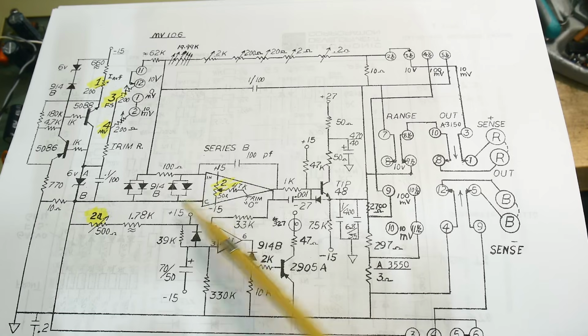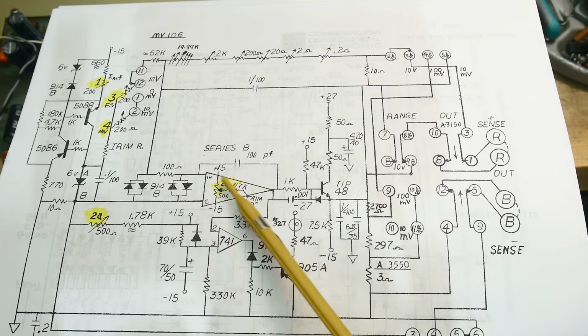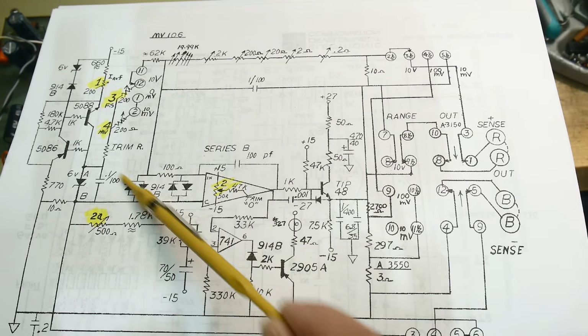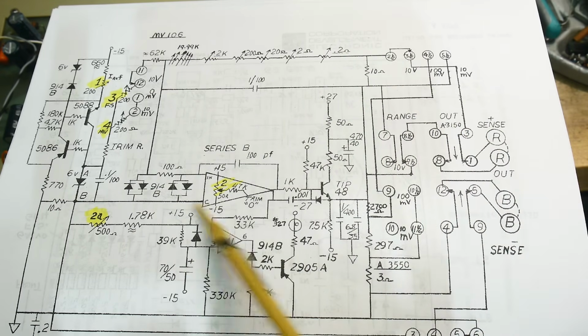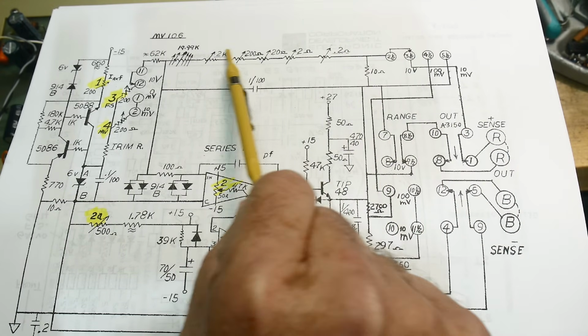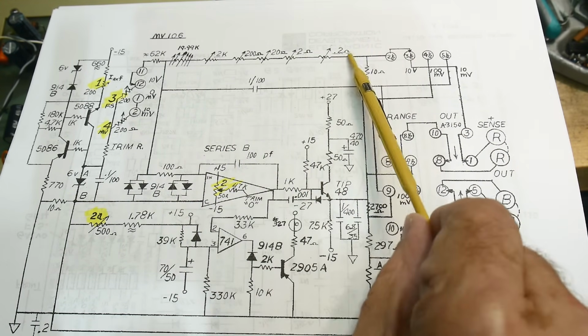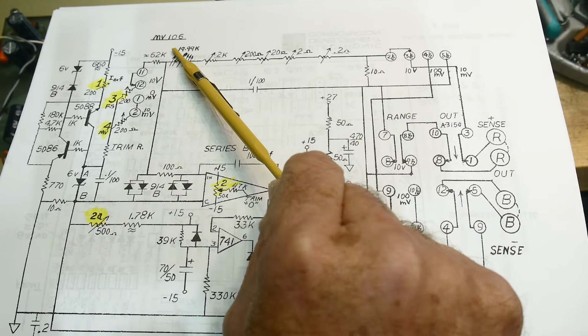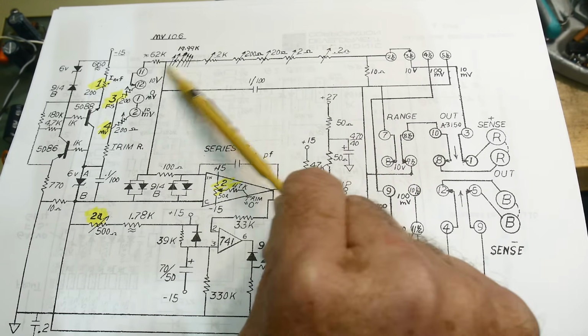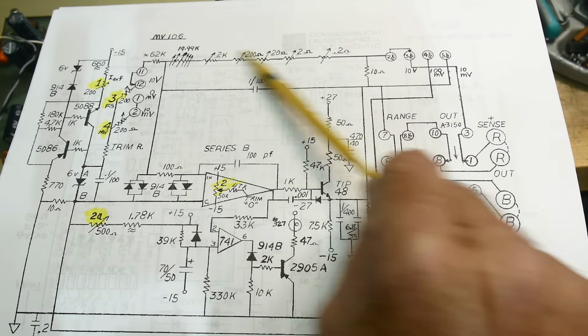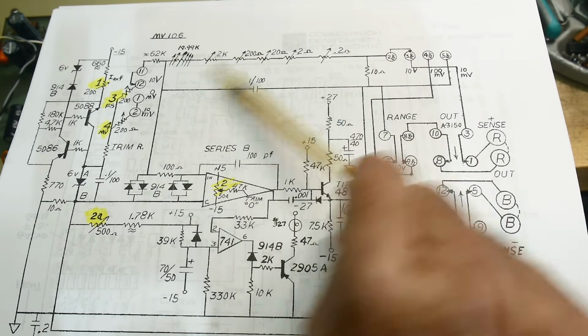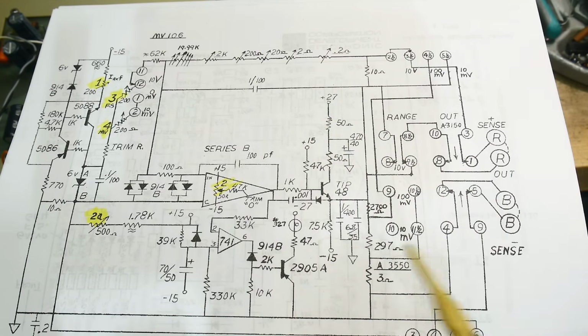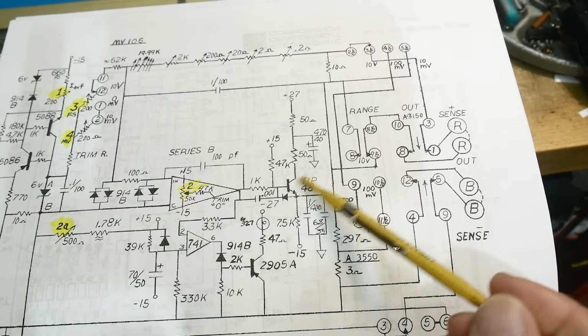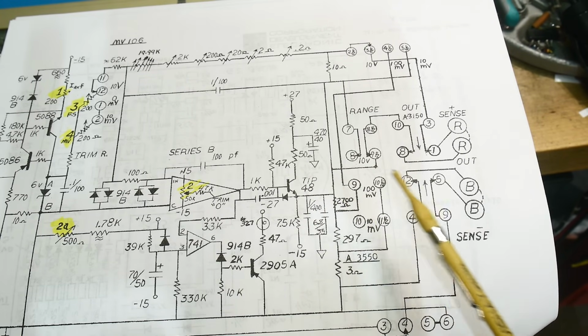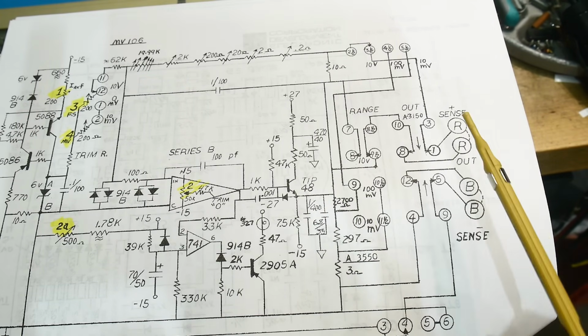Your reference voltage goes into an amplifier, and that amplifier has a big feedback path. And that feedback path goes through all of the switches on the front panel, okay? And it goes all the way from 20K to 0.2 ohms. And all of those are decades of resistors, and that's the loop that you set. And then you get accurate volts on the output. The output comes through an emitter follower here to make it nice and stiff.